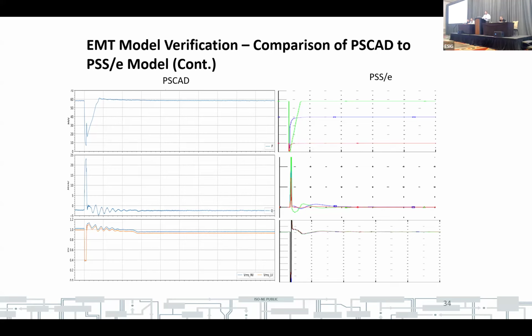Same thing in the reactive output and the green plot. You see some oscillations in the PSCAD that you don't in the PSSE. The oscillations here specifically are coming from the addition of a synchronous condenser. But the reason we don't see them in PSSE is because there we have a much larger network, whereas in PSCAD we've cut the boundaries and put voltage sources at those boundaries. So you don't always get the same dynamics between them, but again, the overall average response does look very similar.